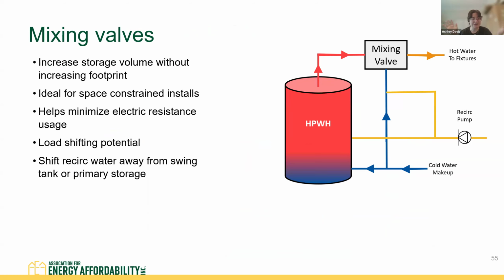So again, like with the unitary situation, installing a master mixing valve at the building is really important with a central plant. Again, it increases that effective storage volume, gives more load shifting potential, and it helps shift recirc water away from the swing tank back to the mixing valve instead, which can help minimize the electric resistance usage. So also pretty much always required, because heat pump water heaters, commercial sized, tend to produce water that's about 140 degrees, those single pass units. So it's pretty much required to make sure that you're not scalding people.